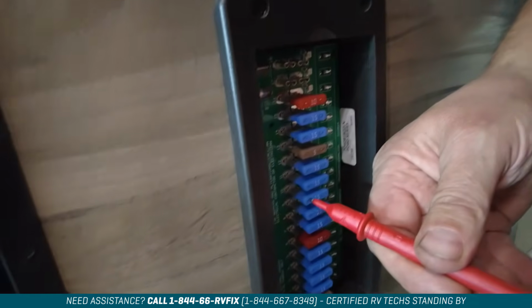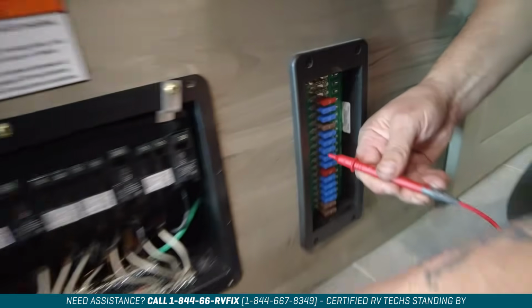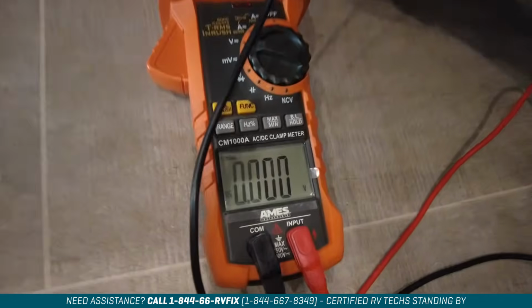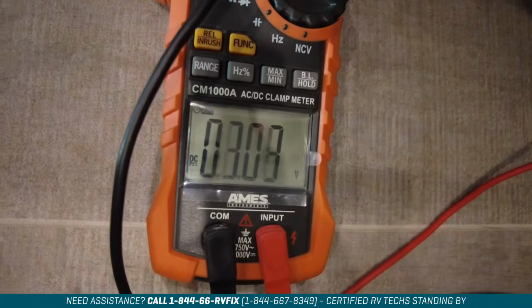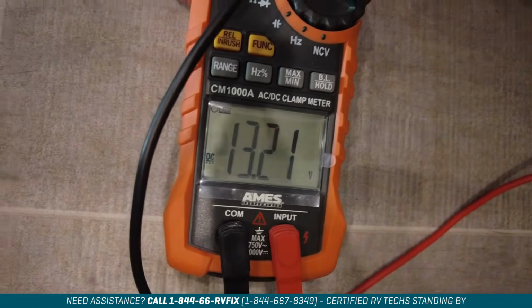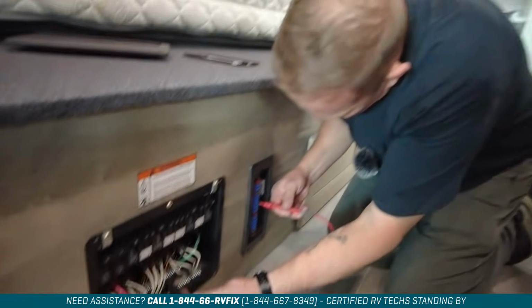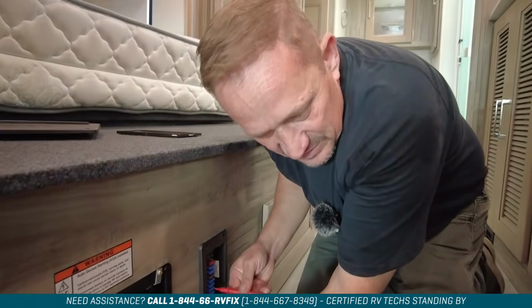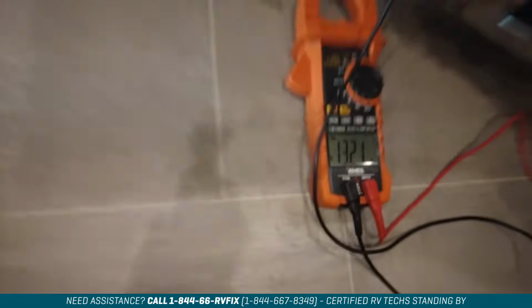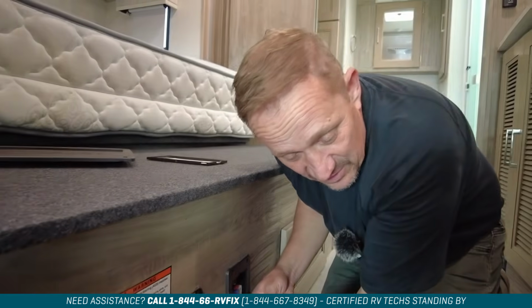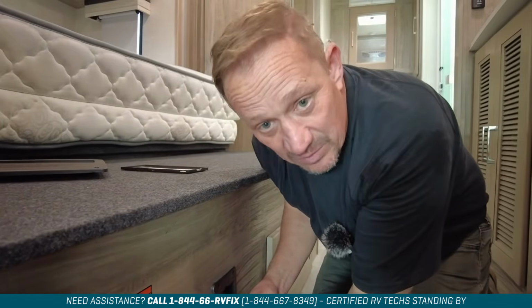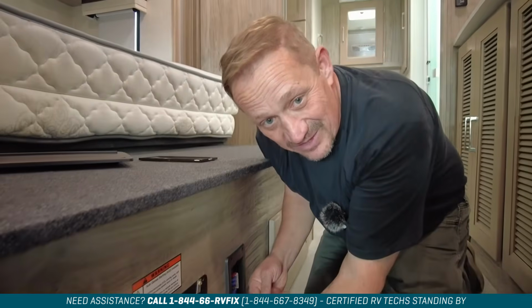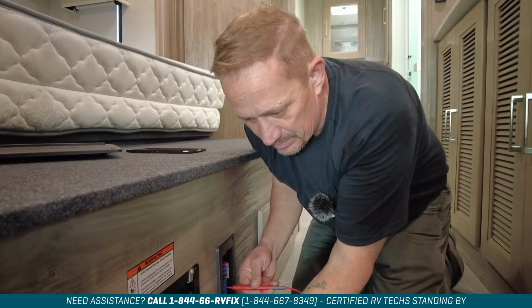If I touch the little metal tab on the end of the fuse, it'll read me that voltage. If I try the metal tab on both sides of the fuse and get the same voltage, I know that fuse is good. If I test one side and have voltage, and the other side I don't, I know I have a blown fuse. I need to change that fuse out and see if that fixes the problem.